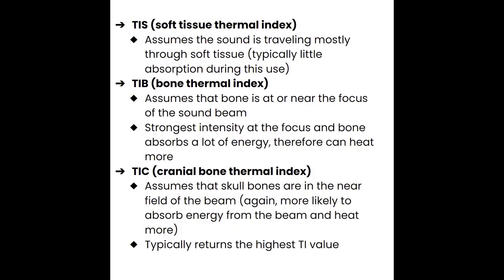So as we were looking at those numbers, you may have noticed the TIS, TIB, and TIC. Those are all referring to different ways to expressing the thermal index. It's going to be more sensitive to changes that occur when the sound is interacting with different types of tissue. TIS is the thermal index as the sound is interacting with soft tissue. So if you're doing a thyroid, an abdomen, a first trimester ultrasound, we're looking more at the TIS.